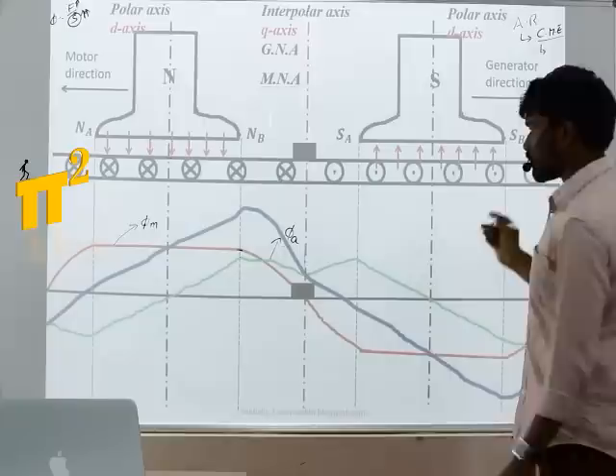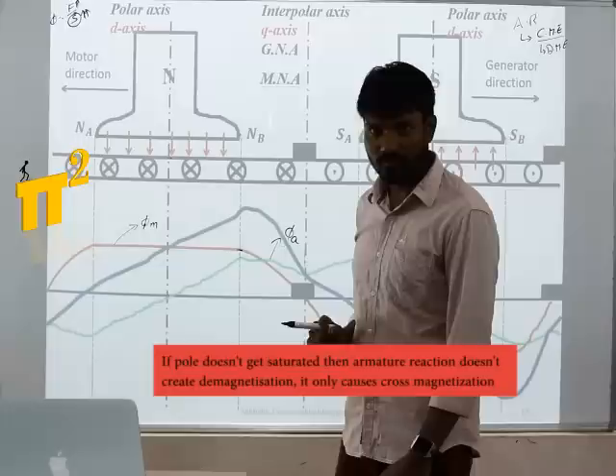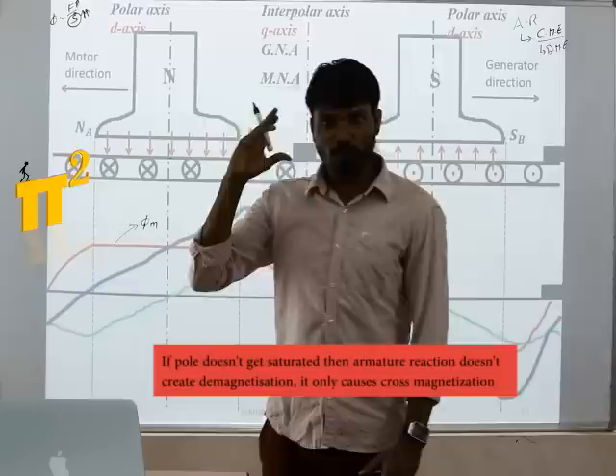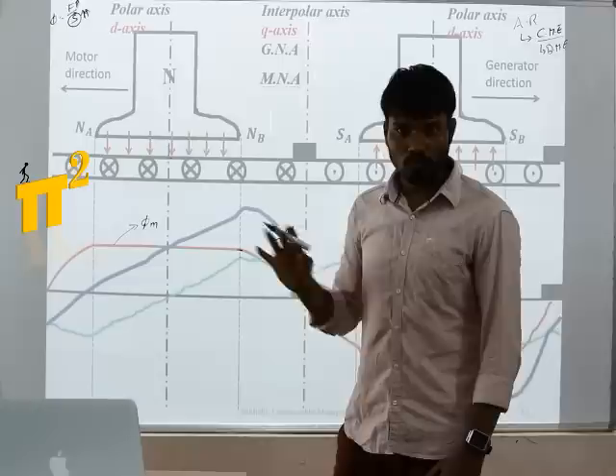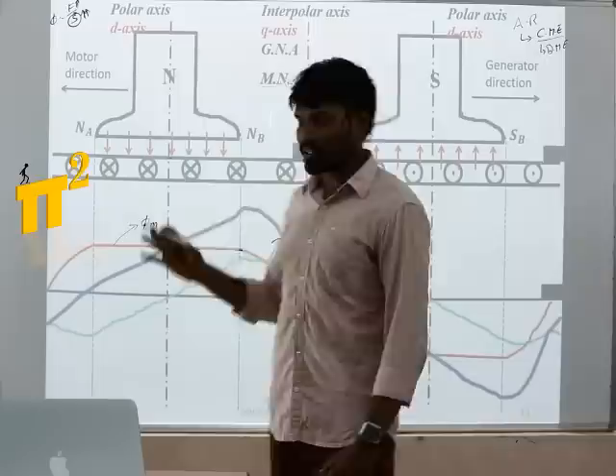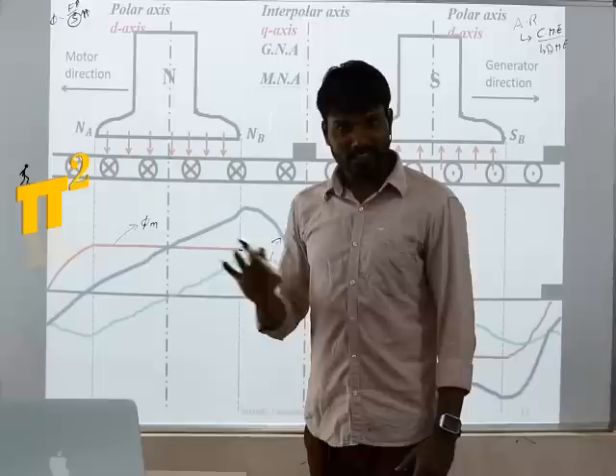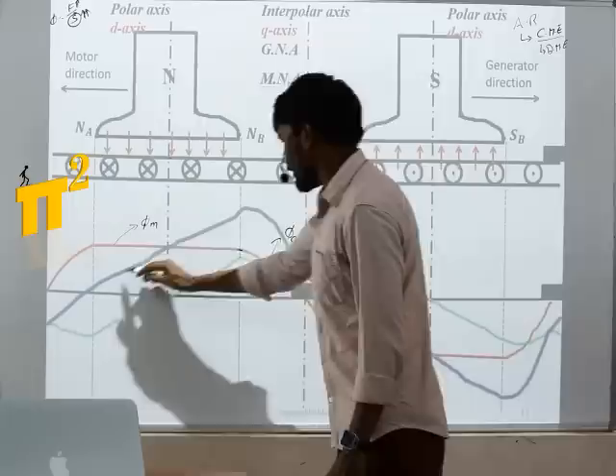To summarize: armature reaction causes primarily a cross-magnetizing effect. Due to this cross-magnetizing effect and saturation of the pole tip, there is also a demagnetization effect. The resultant flux in the air gap is of a peaky wave shape. Different wave shapes: main field flux distribution is trapezoidal, armature MMF is triangular and maximum along the brush axis, armature flux is saddle-shaped, and the resultant flux φM + φA is a peaky wave.